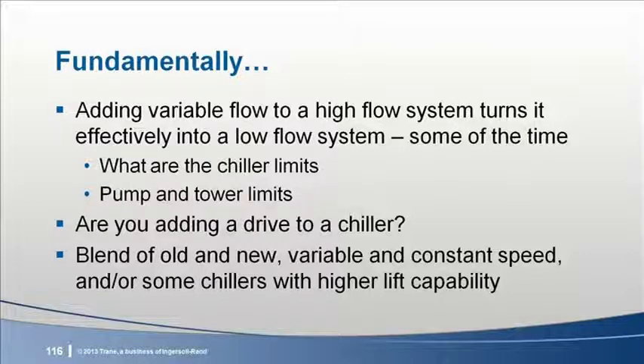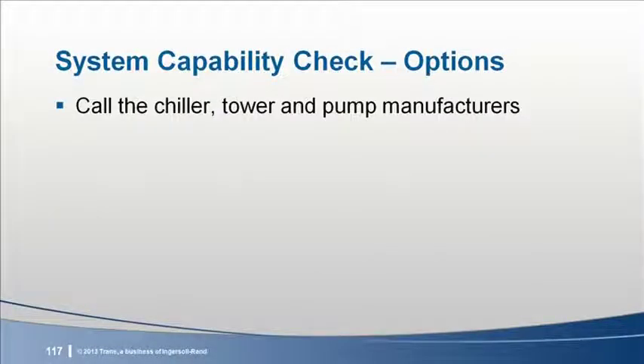Finding constraints on an existing chiller may be unnecessary because many times this conversation comes up when a new chiller is being selected. This opens the door to a lot more options. Chances are good, though, that you'll be asked to preserve some old chillers while either upgrading or buying new chillers that sit next to them. And so your design and operating sequence of operation would need to accommodate a mix of variable and constant speed chillers and/or a combination of chillers that have different limits. Before you pass go and collect $200, your first calls are to the original equipment manufacturers to find out the theoretical limits of your equipment. So you'd call the chiller, tower, and pump manufacturers, and hopefully also the engineers of record on past plant designs.